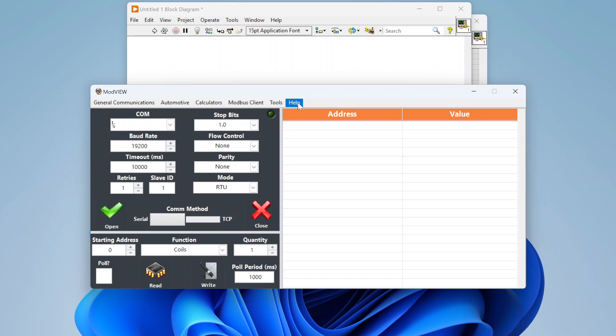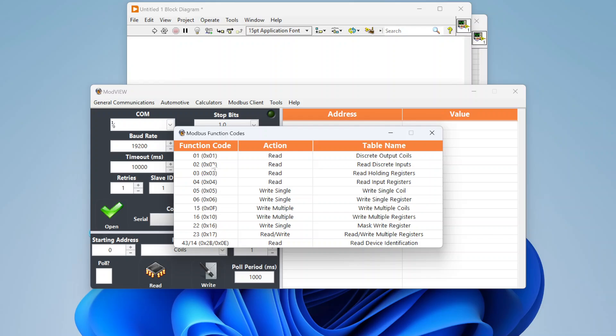There are different methods by which you can access this data, and Modbus refers to those as function codes. Each function code is assigned a number — for example, reading discrete inputs is function code 2. There are different types of data: coils, discrete inputs, holding registers, and input registers. Depending on the function code, there are different levels of access — read, write, or both.